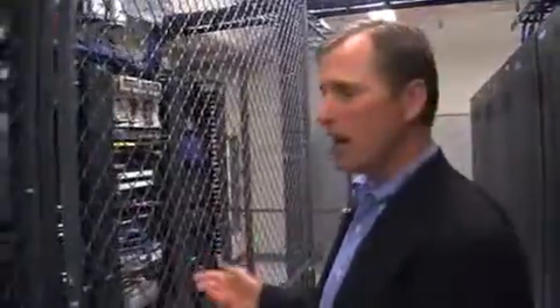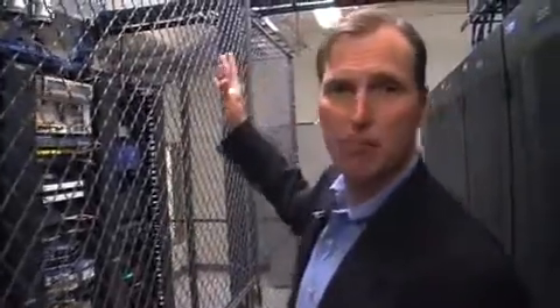This is the MDF, which is really the heart of the data center. This is where all the network comes in and comes through redundant switches, and we distribute that out to customer equipment. So we have 3 separate fiber providers with 3 separate entrances into the building right now. That's XO, Time Warner, and Qwest. Every provider is in a separate conduit and comes in a separate entrance of the building. We travel that conduit and are all terminated here and go through our core distribution switches, as I mentioned, out to the customer cabinets.